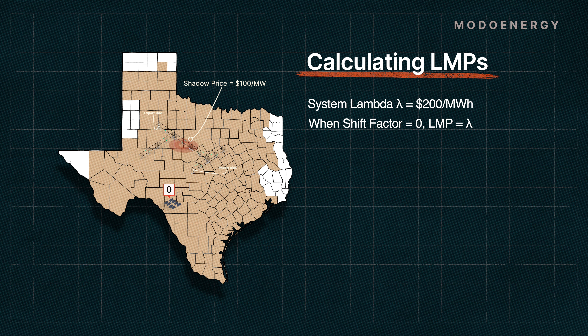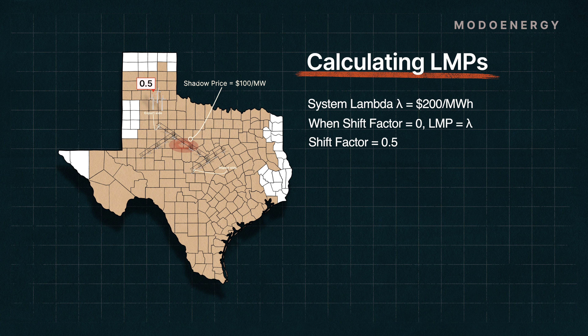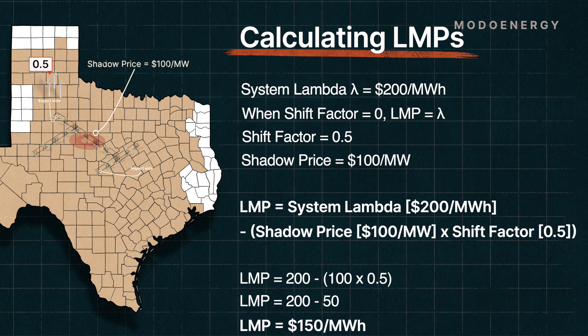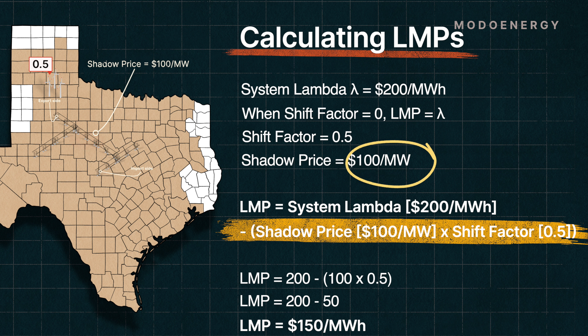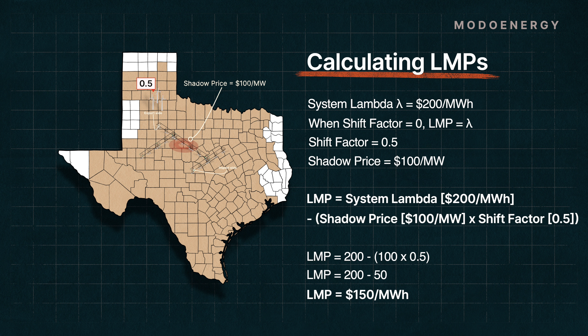Now, let's go back to the generator we introduced before, near the export side of the constraint, and remember that it has a shift factor of 0.5. Its LMP would be calculated by multiplying together the shadow price of the constraint — let's say this is $100 per MW — and the shift factor of the generator, and then subtracting that entire value from the system lambda. Therefore, at this settlement point, the price is lower than the system lambda, with a value of $150 per MWh.